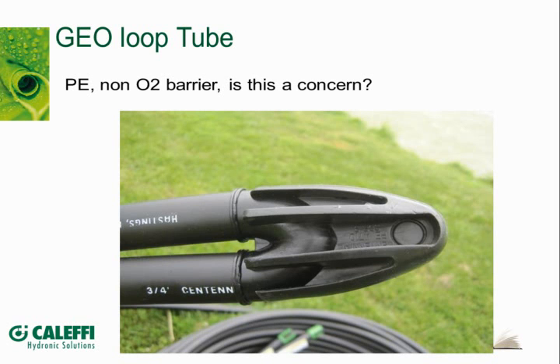This could be a matter of academic question. From my personal experience, I feel corrosion from O2 permeability is more of an issue at higher temperatures than at low temperatures, because the solubility of a metal doubles with every 10 degrees rise in temperature. Since all our geothermal installations operate between the mid-20s and as high as perhaps 100 degrees, we're less likely to see those issues. But with geothermal, I really feel the original quality of the makeup water is the determining factor in how that system behaves, as well as the fluid—if it's an antifreeze fluid, being good quality with inhibitors blended with the water, not just pond water with some methanol in it like in the first example. The presence of inhibitors in the makeup fluid is the big determining factor.